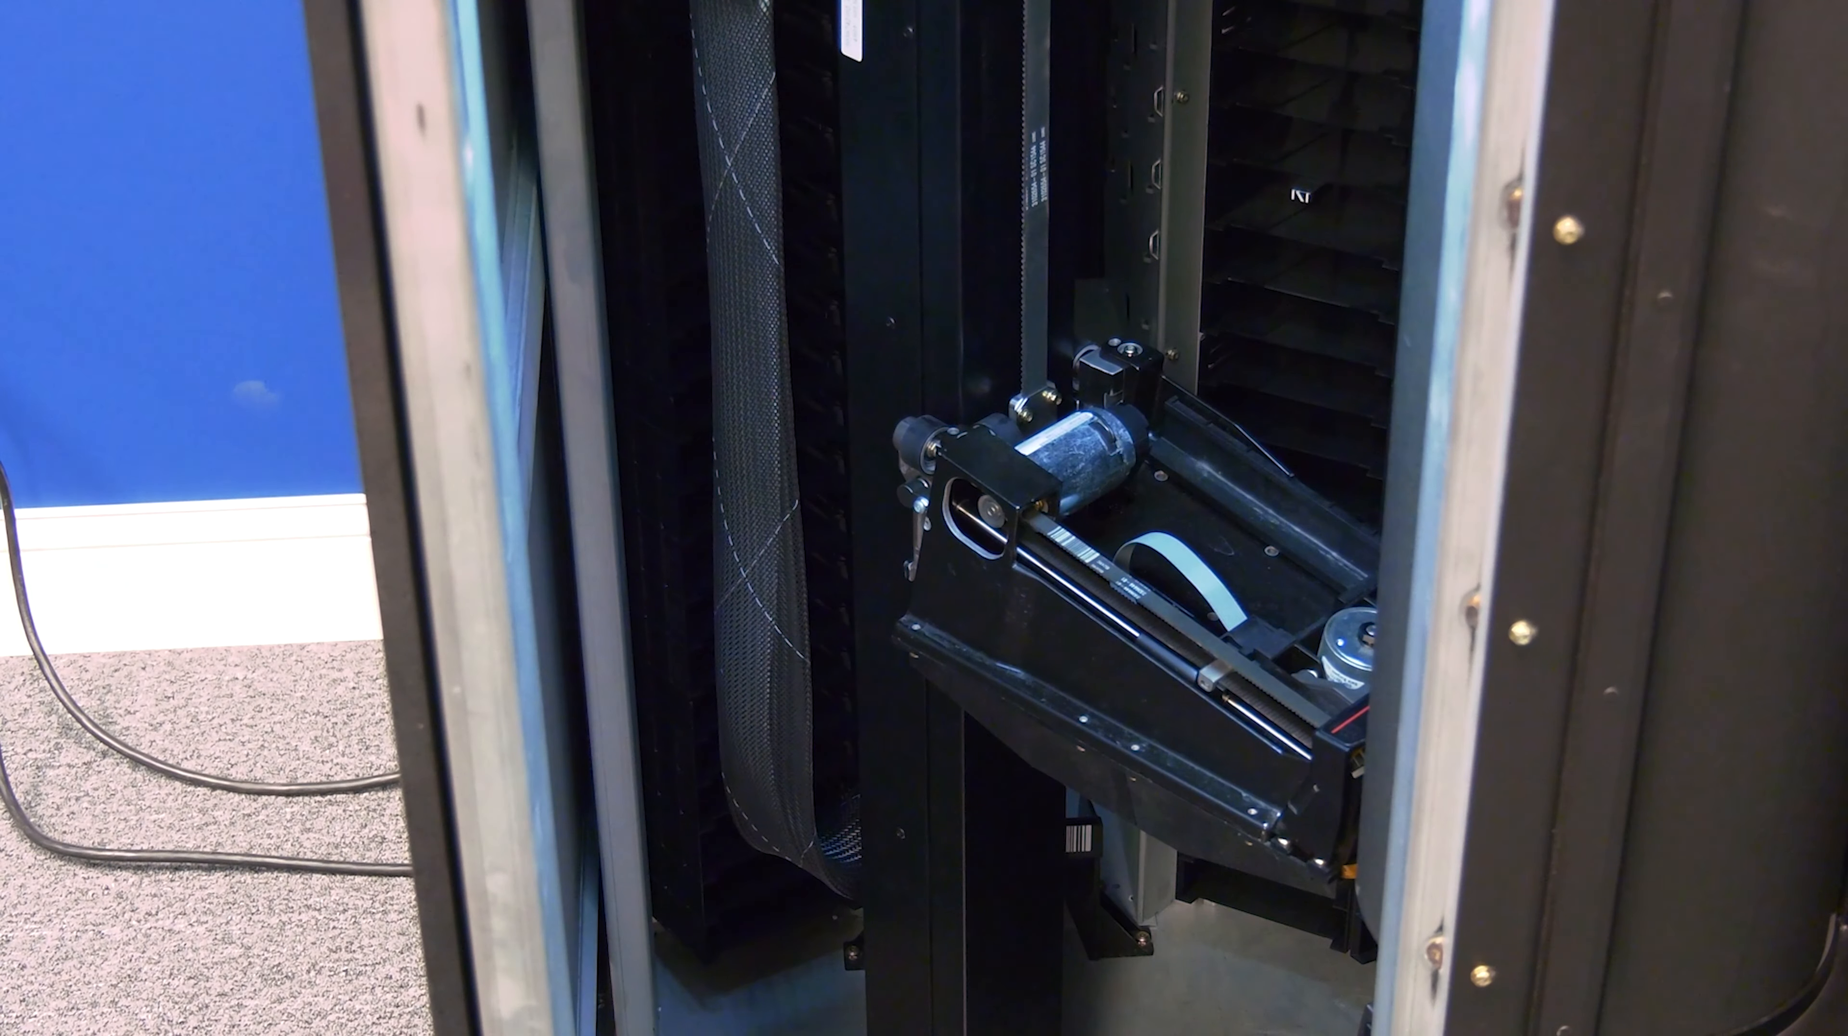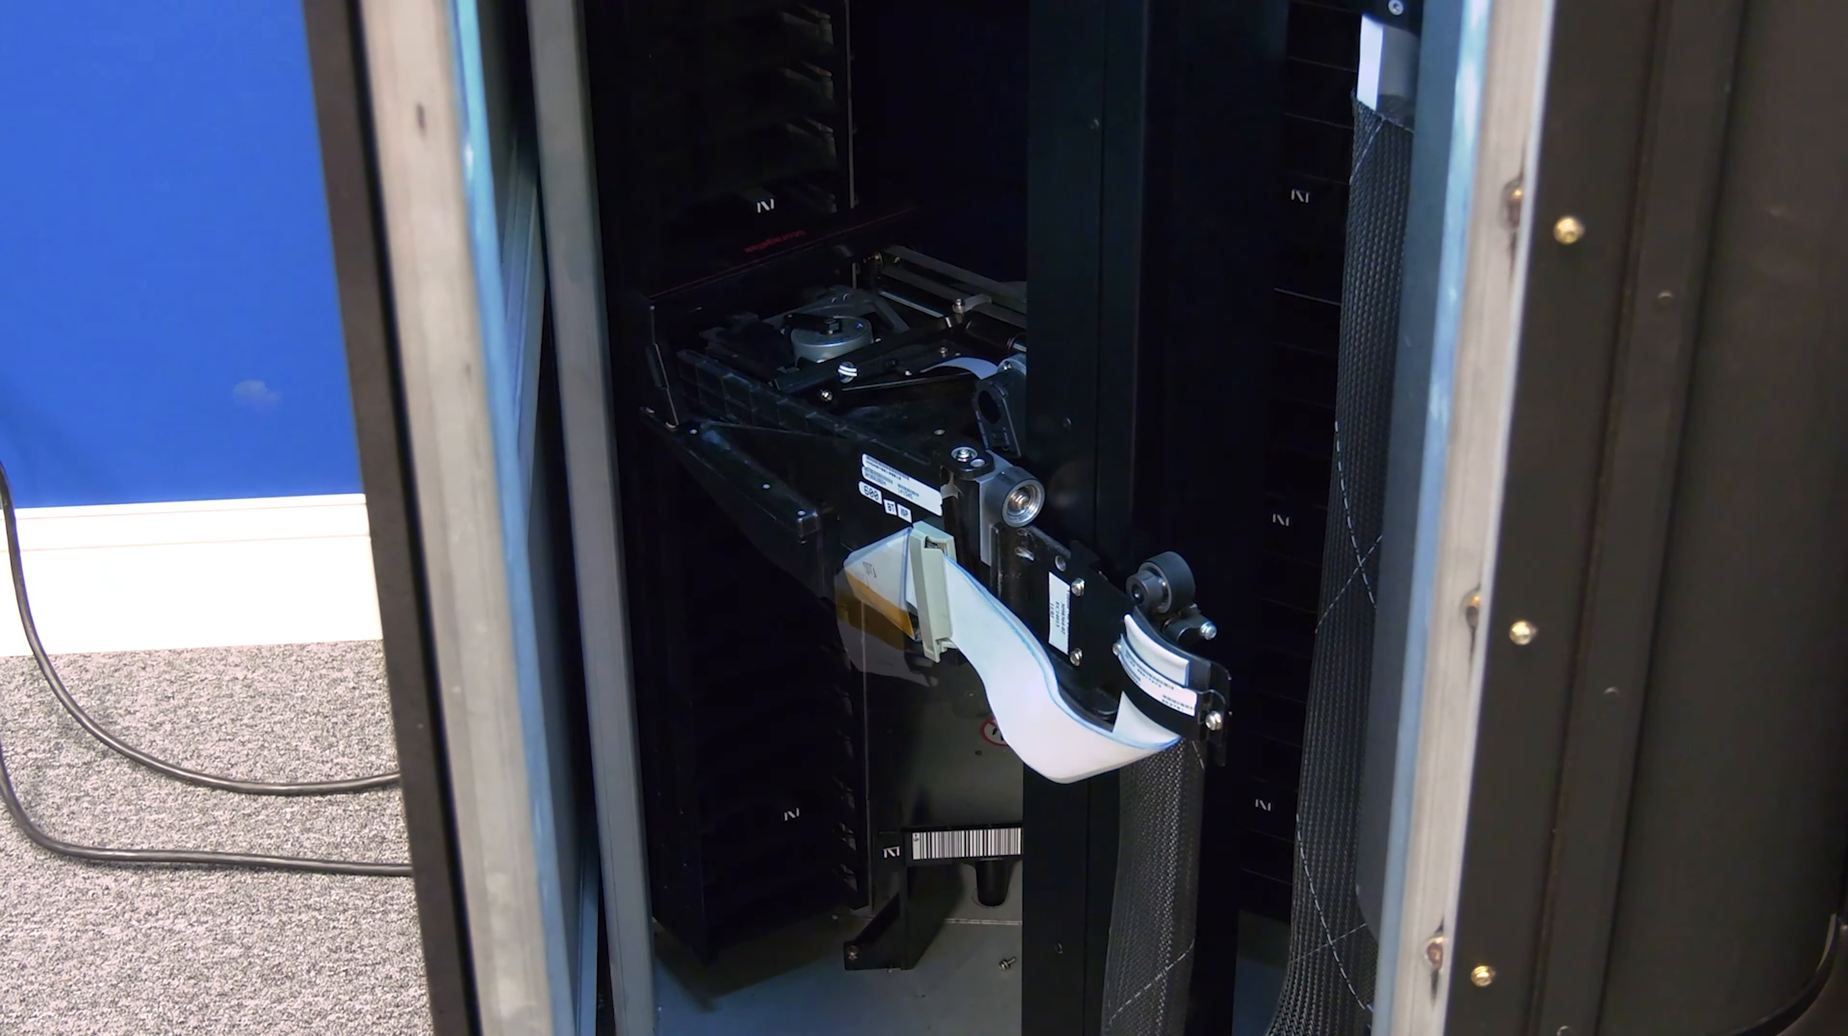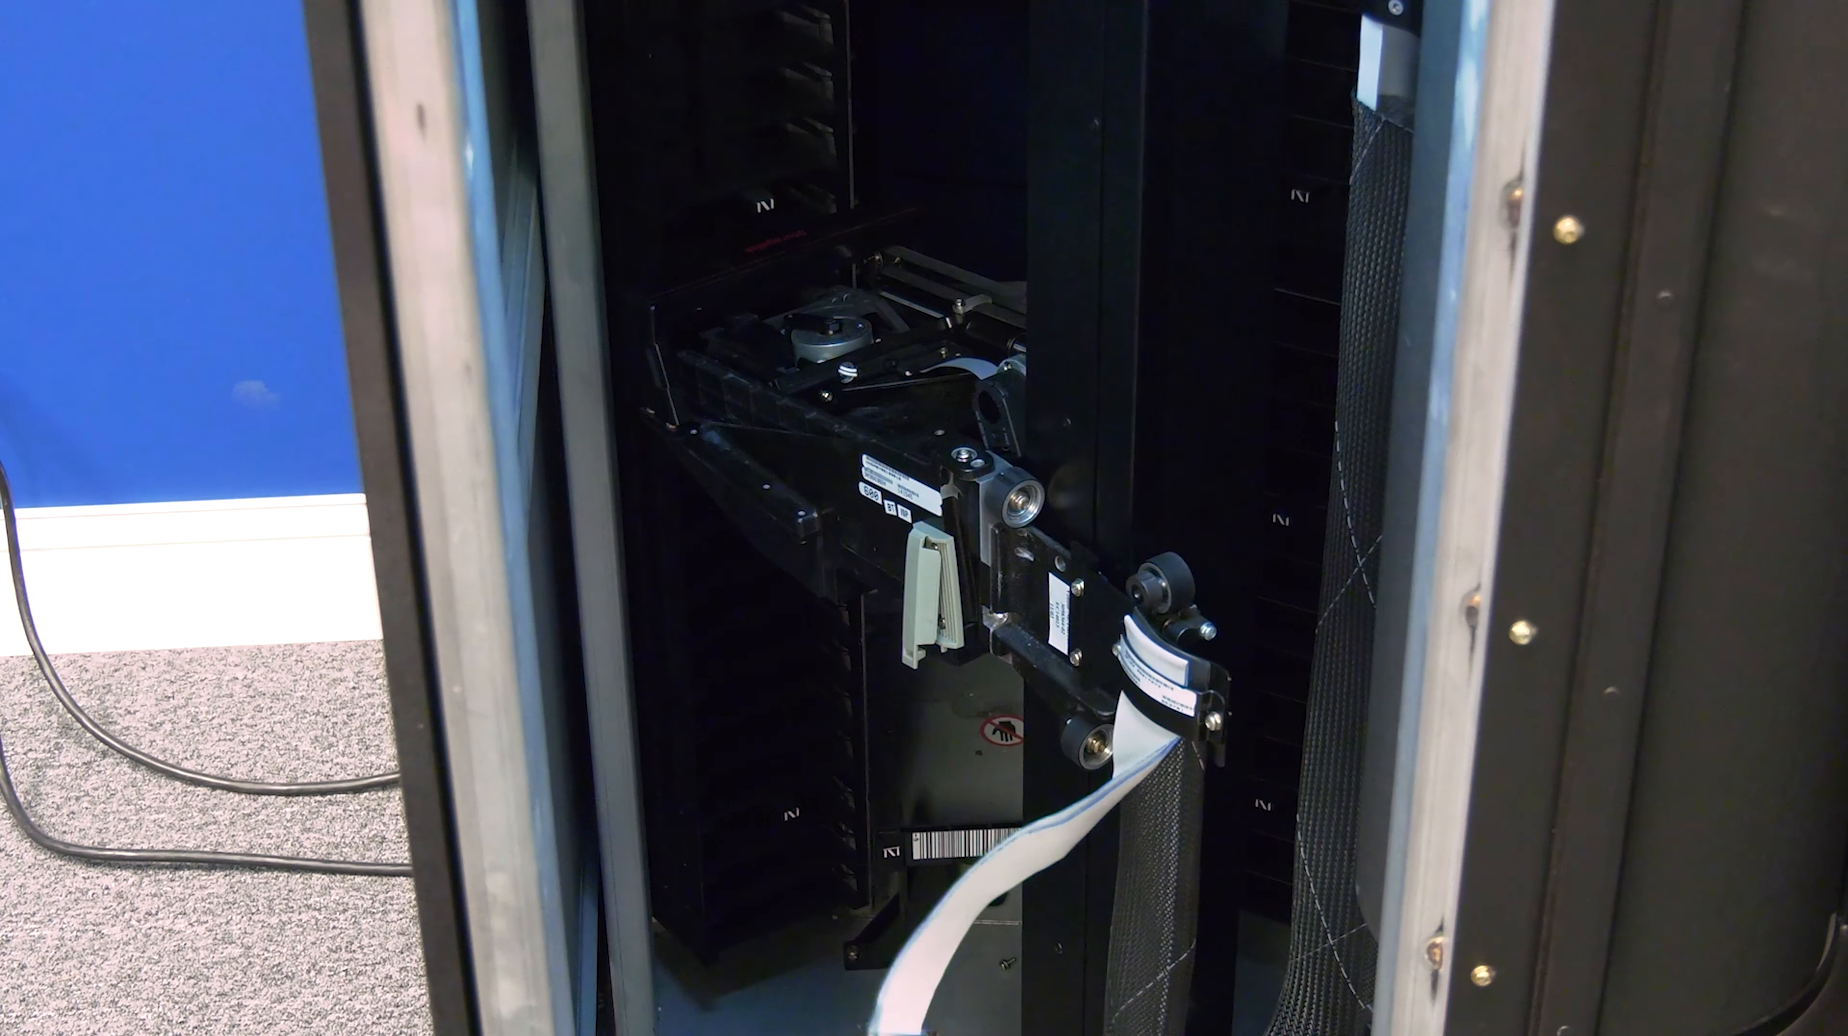First, you will need to spin the picker around so that you can see the ribbon cables that go to the picker. These will need to be unhooked from the underside of the picker assembly. To do this, squeeze both sides of each connector simultaneously to release it from the bottom of the picker. Once both cables are unhooked, you can also undo the clip that holds them and carefully pull them out of the way.